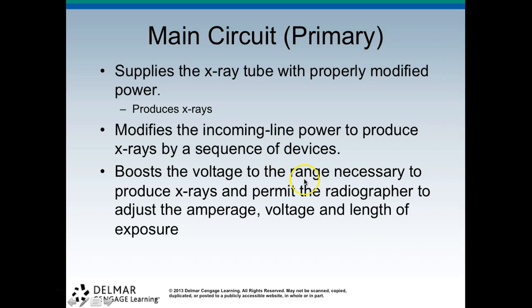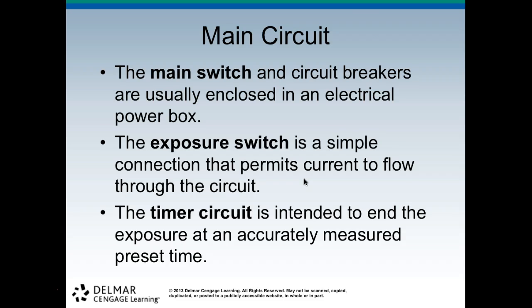All right, so the main circuit, the primary circuit, supplies the X-ray tube with properly modified power, so that's what produces our X-rays. It modifies the incoming power to produce X-rays by a sequence of devices. It boosts the voltage to a range necessary to produce X-rays and permits the radiographer to adjust the amperage, the voltage, and the length of the exposure. The main circuit has the main switch and circuit breakers that are usually enclosed in an electrical box. The exposure switch is a simple connection that permits the current to flow through the circuit, and the timer circuit is intended to end the exposure at an accurately measured preset time.